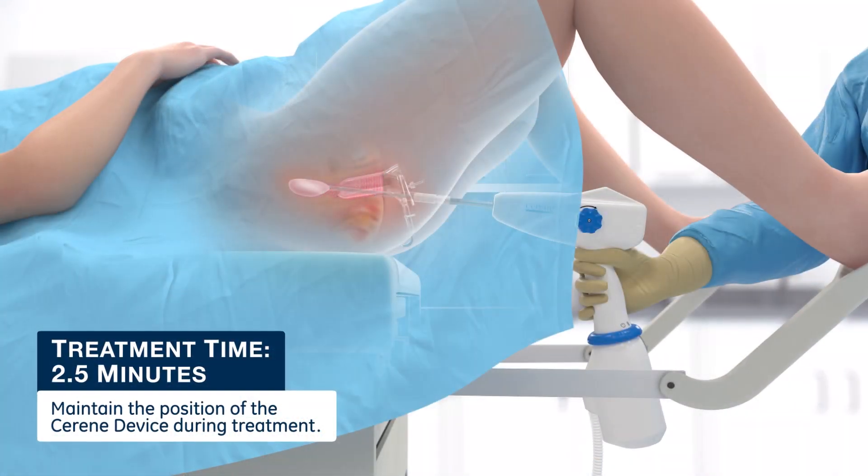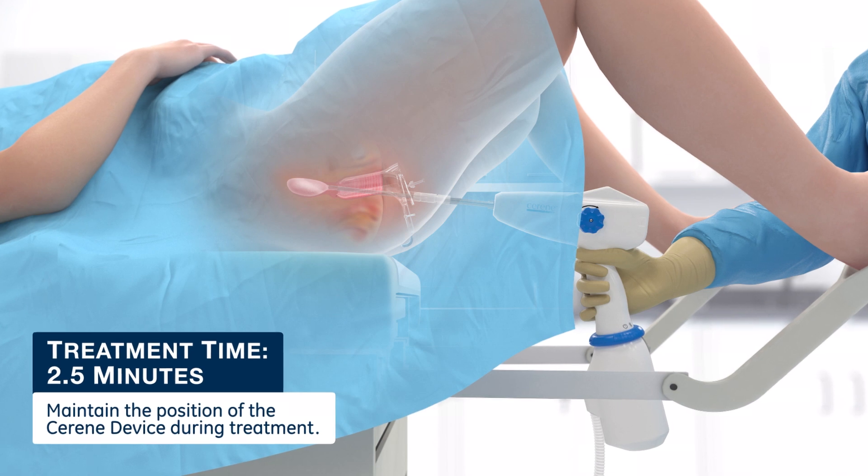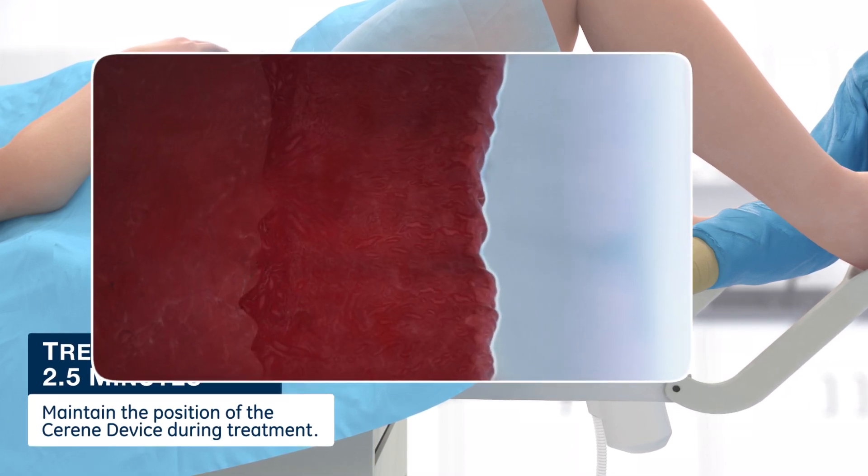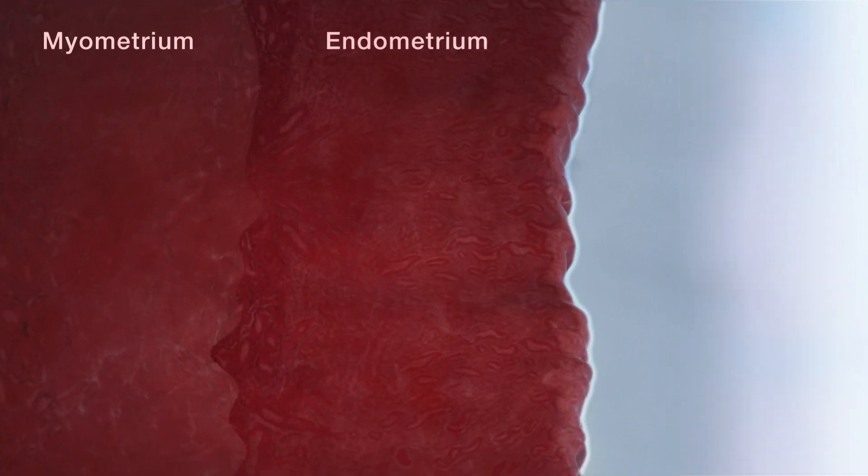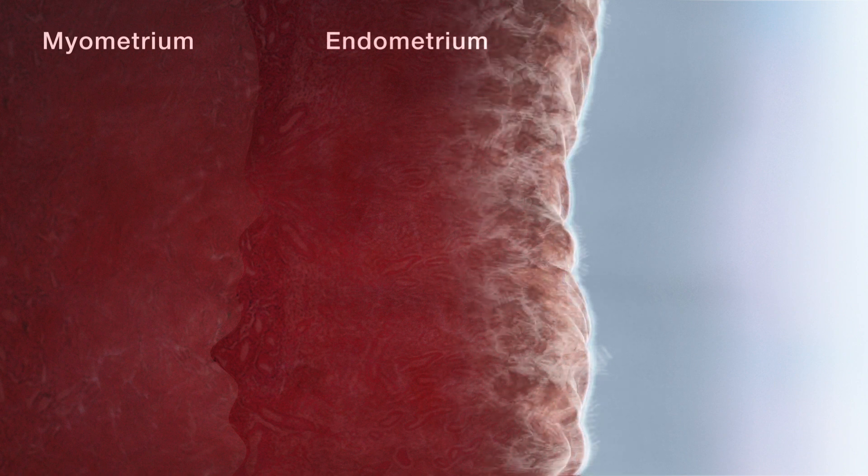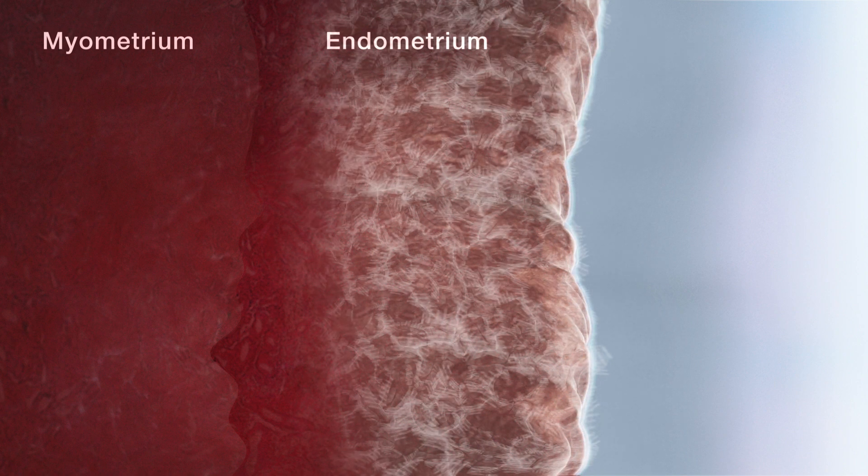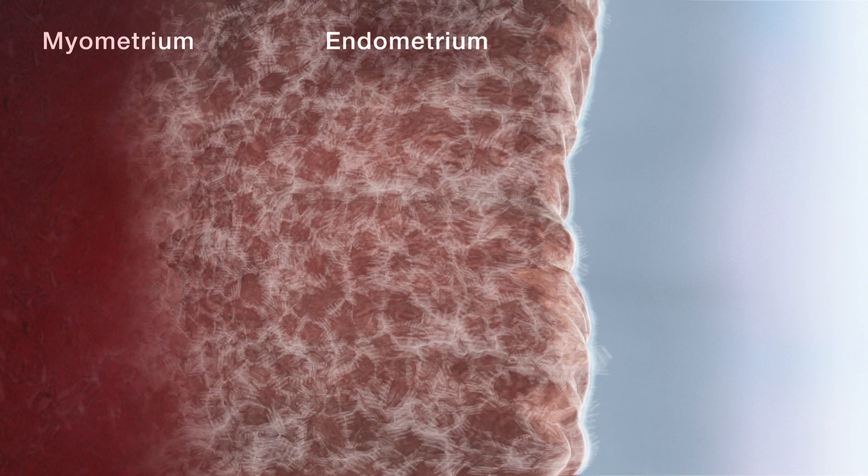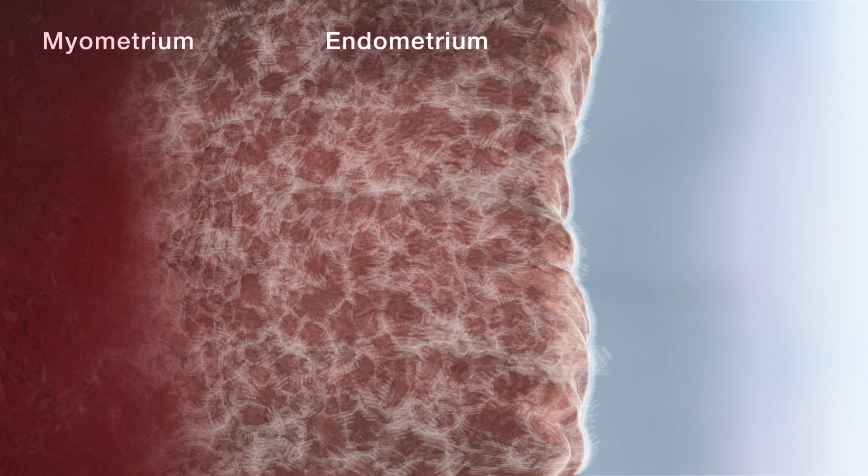Maintain the position of the Cerene Device during treatment. Once treatment is initiated, cryothermic ablative temperatures and the analgesic effect accompanying them occur within seconds. The nitrous oxide is evenly distributed within the liner to achieve consistent cavity coverage and depth of ablation.